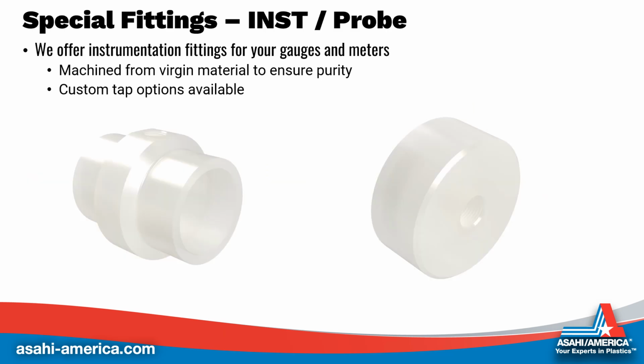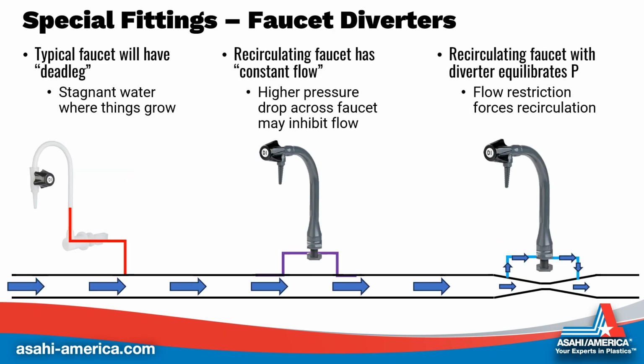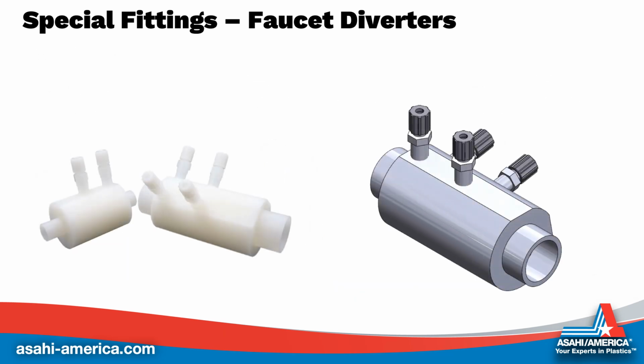We offer instrumentation and probe fittings to facilitate installation of your gauges and meters. These fittings are machined from virgin material to ensure their purity, and while we do have a range of standard tap options, custom requests are welcome. Standard faucets will likely have dead legs or areas of stagnant water where bacteria can build up and become biofilm. Recirculating faucets attempt to combat this with constant flow, preventing stagnant water areas. However, there is the possibility that stagnant areas may still exist due to the pressure drop across the faucet. This is why we offer recirculating faucets with a diverter, which restricts flow across the faucet, increasing pressure to maintain steady flow.